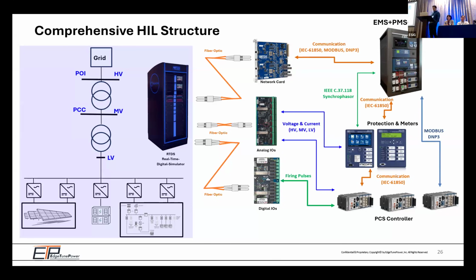For example, the PCS controller is sending firing pulses through digital inputs to the real-time simulator. The real-time simulator is sending voltage and current as analog output back to the PCS controller. We tested the protection. Why? I tried to create a problem in the first slide, because if you do not have protection and control coordination between the controller and the protection, no matter how good your controller protection is, if it's going to trip too early, you cannot fully utilize your system for your client.